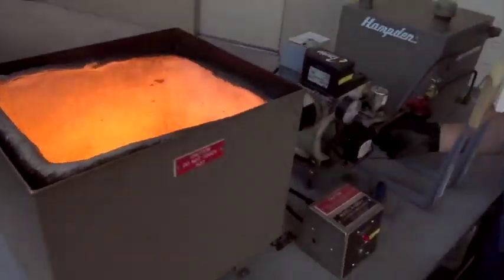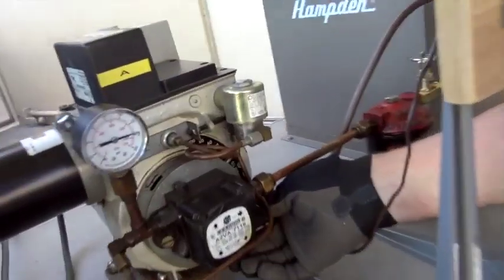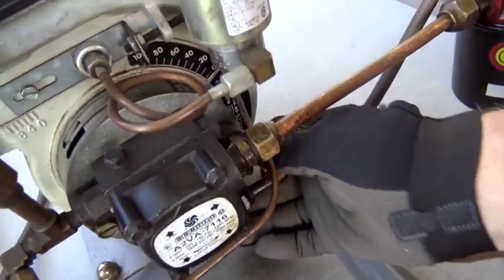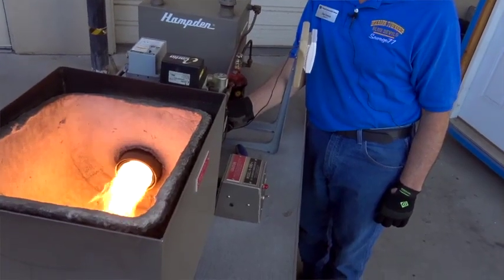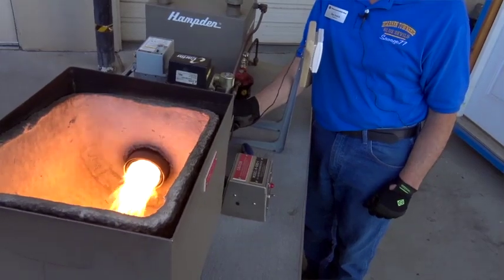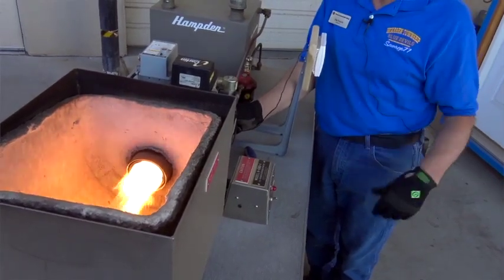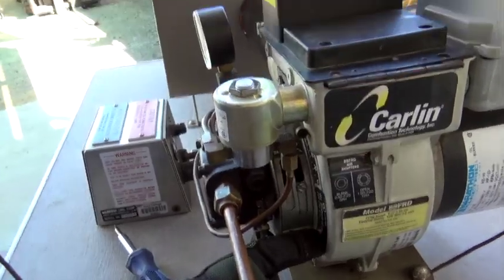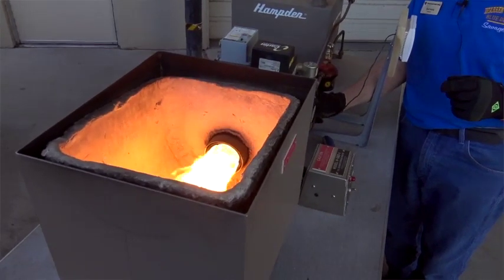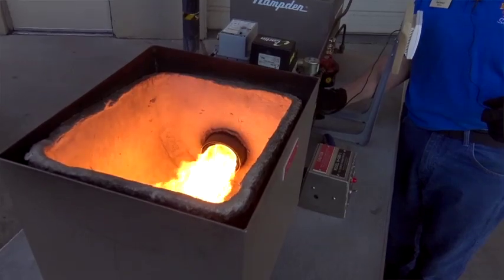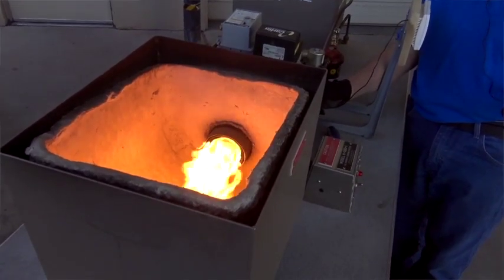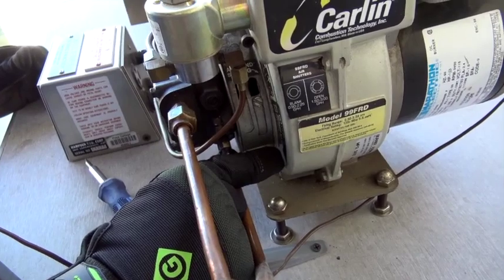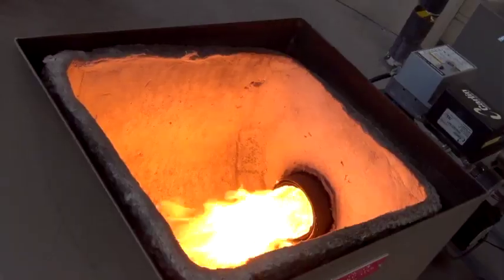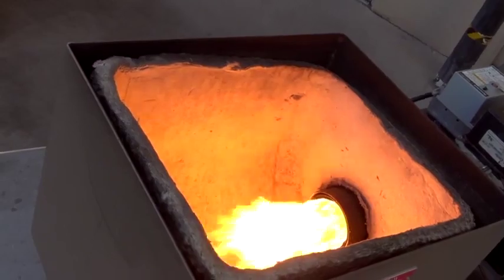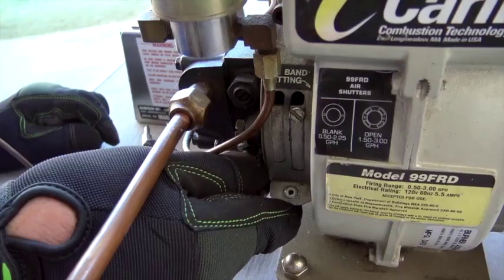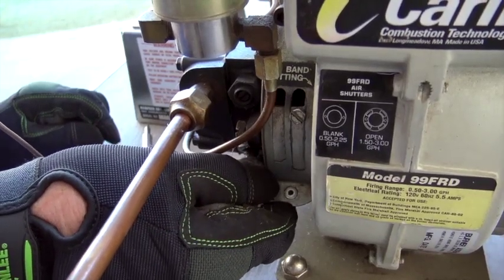Now I'm going to adjust this primary air. As you can see, I am moving it wide open. And as you can see, that smoke and that flame over there. You can see the flame, how bad it is right there, because we're getting too much combustion air. Now I'm going to slow it down and choke that air off a little bit. Now I'm getting a better feather of the flame. I'm getting a good ratio of combustion air and fuel.